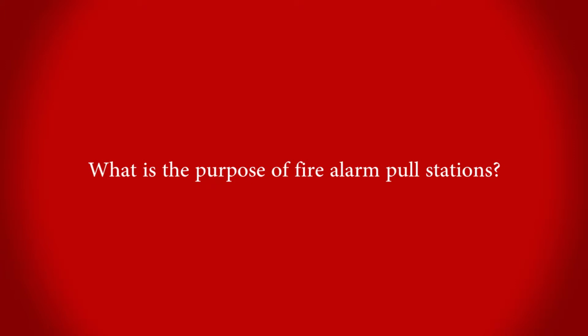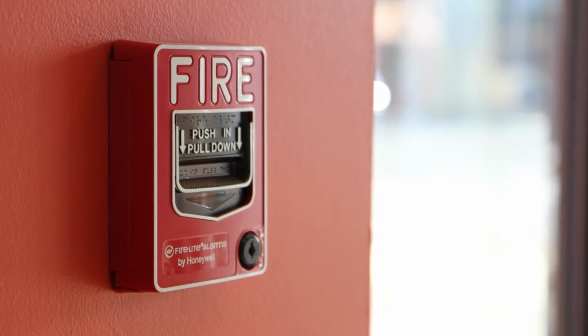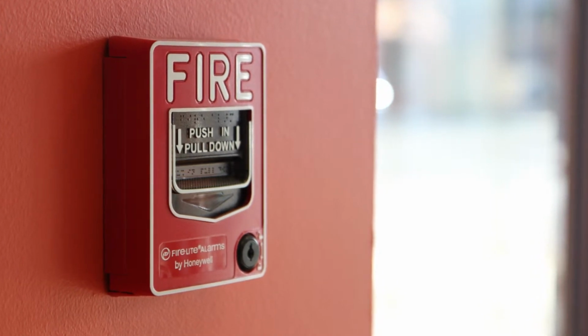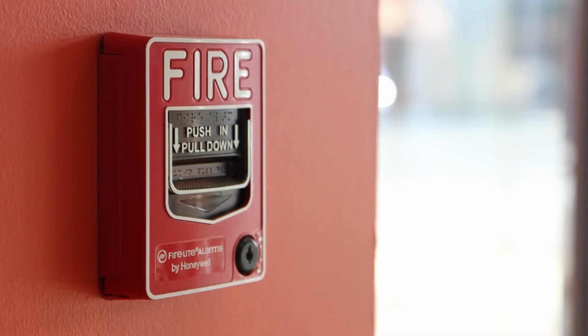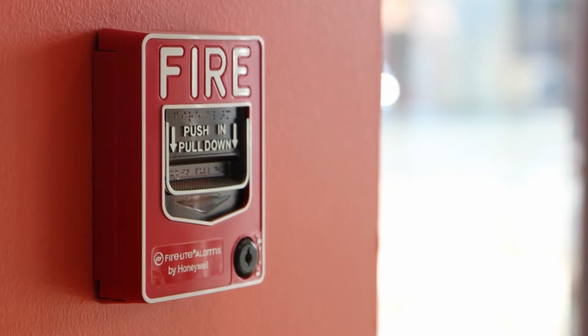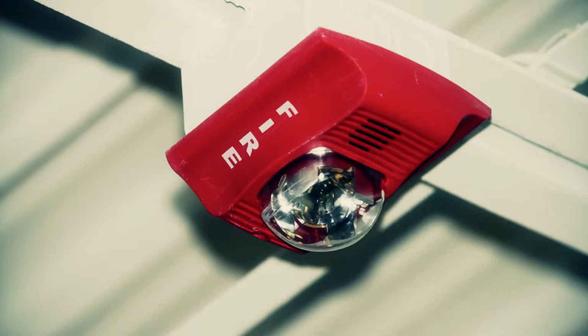A lot of people think that when you go over to the wall and pull that little red lever down, you're going to activate the sprinklers. That couldn't be further from the truth. What you're activating is noise and visual alerts. We have audio visual devices that you'll typically see in schools, businesses, and so forth. By code we strategically put those by exit doors or in the paths of exit so that you can get on your way. You can activate the system, put the building into alarm, and get people to evacuate.